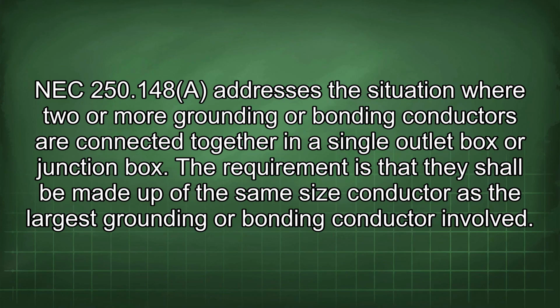250.148 addresses the situation where two or more grounding or bonding conductors are connected together in a single outlet box or junction box. The requirement is that they shall be made up of the same size conductor as the largest grounding or bonding conductor involved.